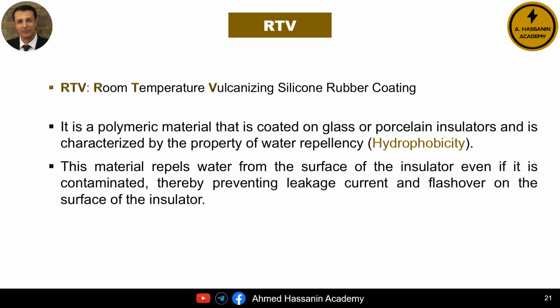RTV is a polymeric material characterized by its hydrophobic property, meaning that it can repel water from the surface of the insulator even if the surface is contaminated with dust. In other words, coating the insulators with RTV makes them behave similarly to silicone rubber insulators, and therefore significantly reduces the problems associated with pollution and flashover.